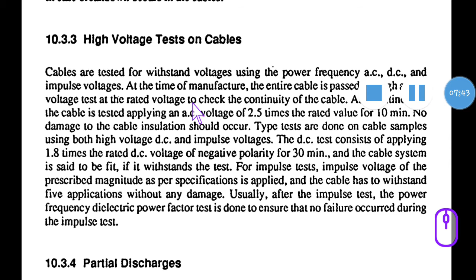If they want to do a high voltage test on the cables, the voltage may be high voltage, impulse voltage, power frequency voltage, or switching surges. Any type of voltage. All those have to be tested in the laboratories, and withstanding capacity is also checked here. Routine tests are done on the cables. If they apply AC voltage, it should be 2.5 times the rated value, applied for 10 minutes, to see whether it will withstand or not. For DC, 1.8 times the DC rated voltage is applied for 30 minutes, to see whether it will withstand or not.